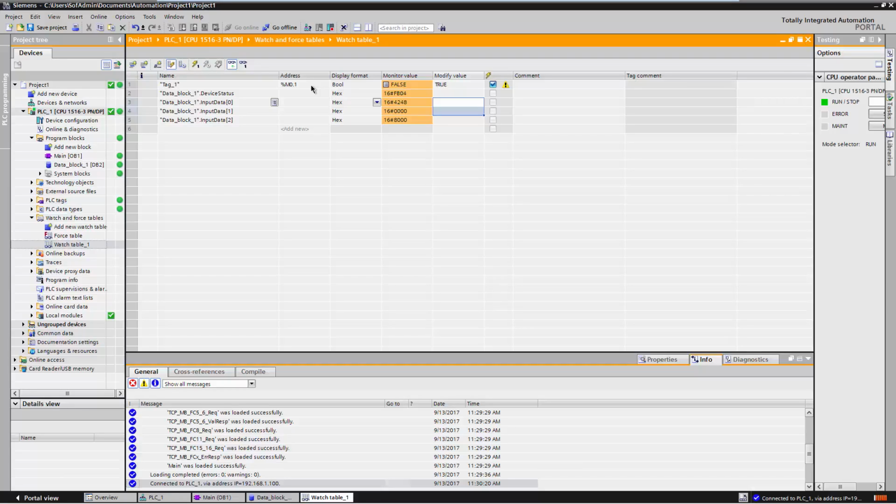The first 2 registers of the input data correspond to the value. The high byte of the last register contains the status. Hex 80 means good. If you click several times on Modify Now, you can see how the data changes.